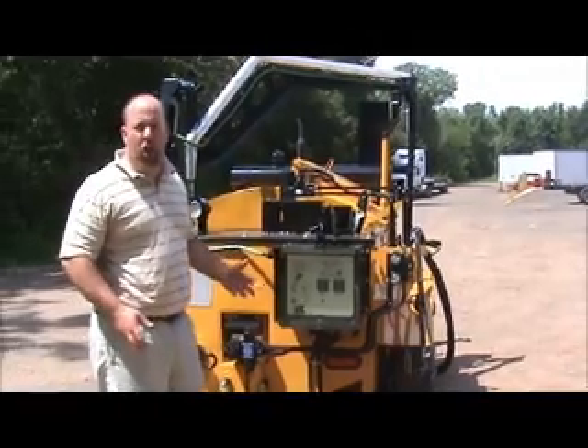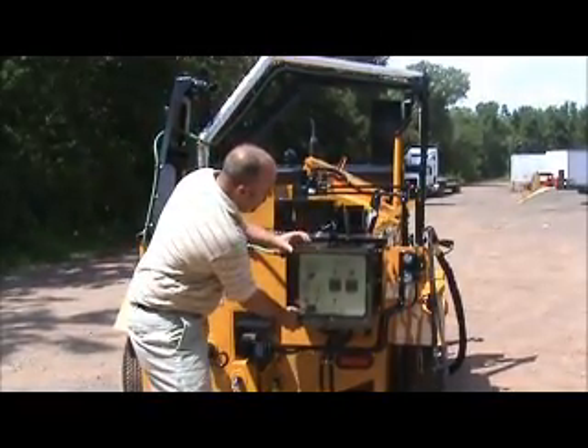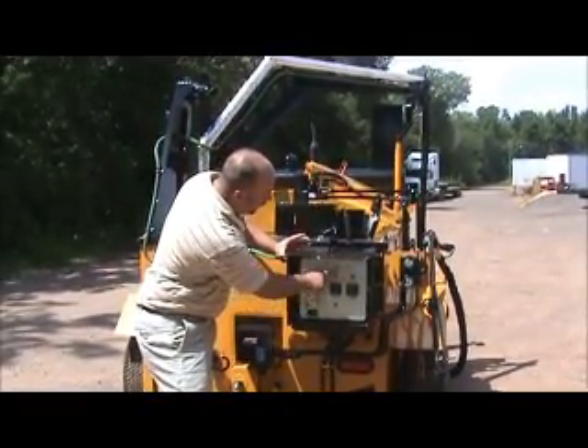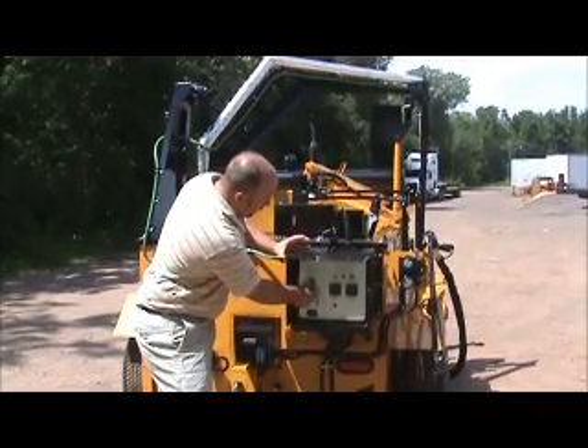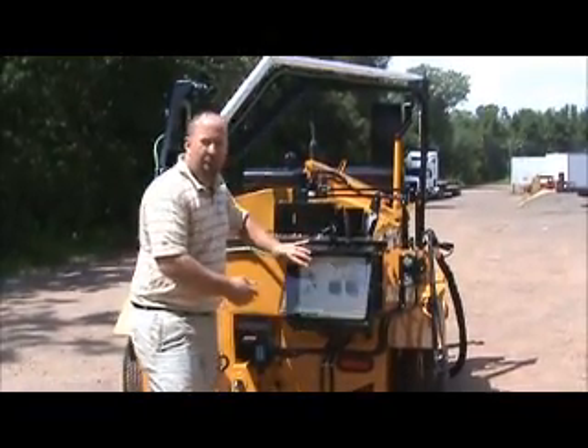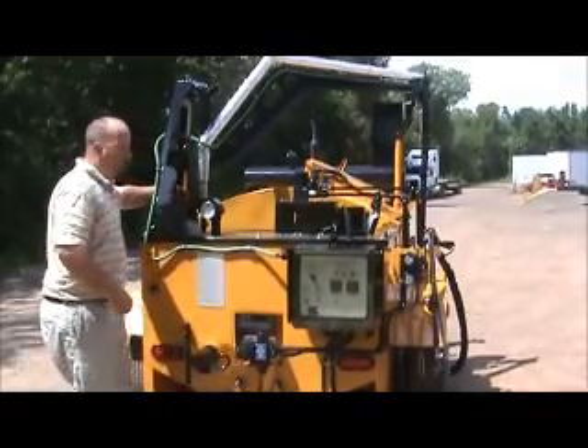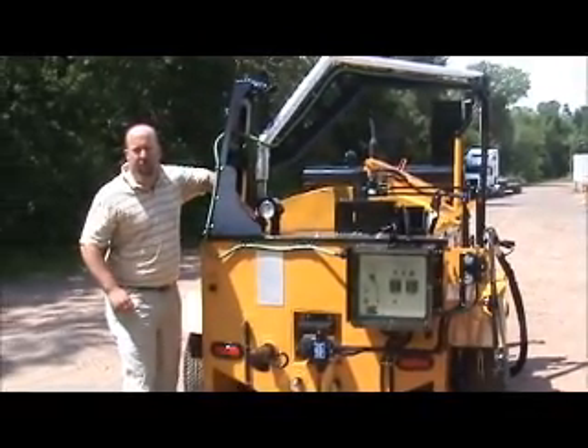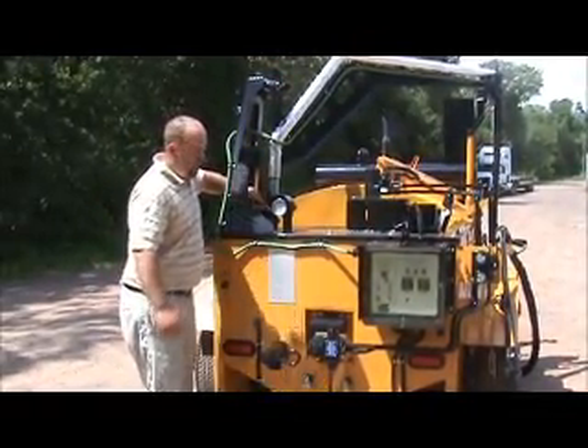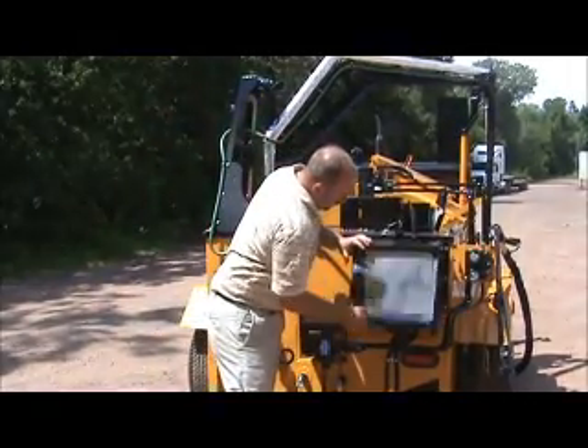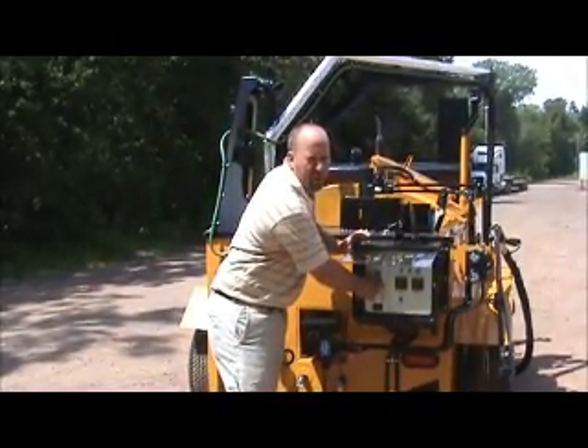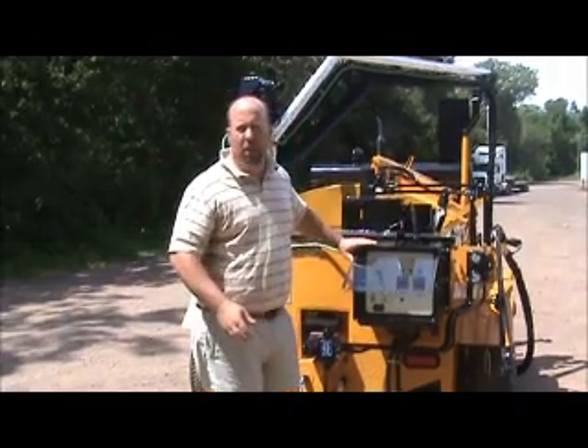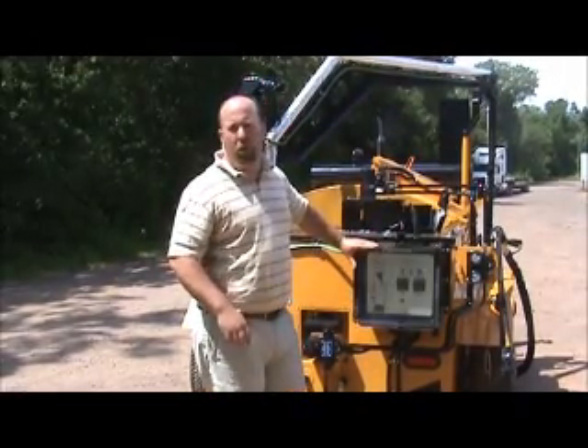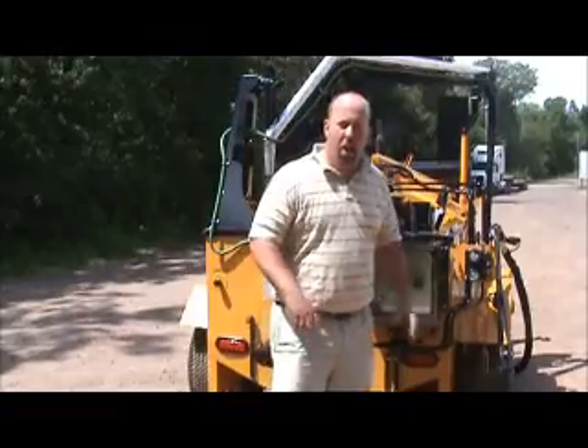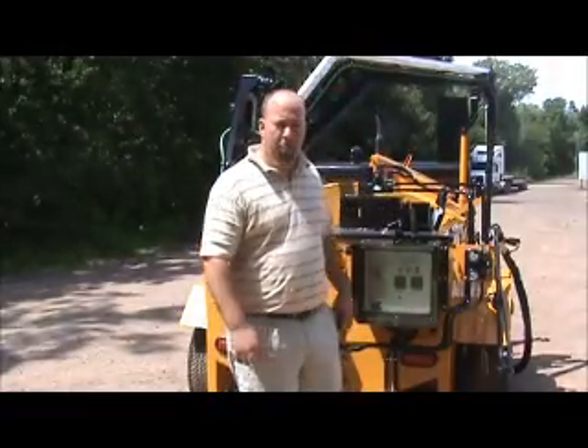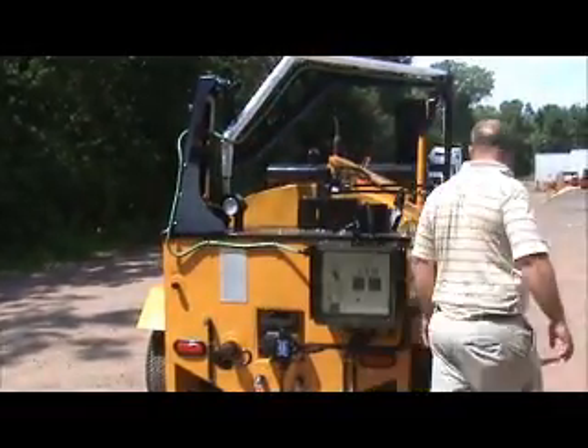I'm going to go through the shutdown procedure. For our shutdown, turn our heat off, turn our burners off, put everything into the neutral position. Then we would come back, put our three-way ball valve, this WPC valve, and then recirculate our pump in reverse for 2 minutes, and then put everything in neutral, shut the engine off on the key. I'm going to shut things down and do our final shutdown.